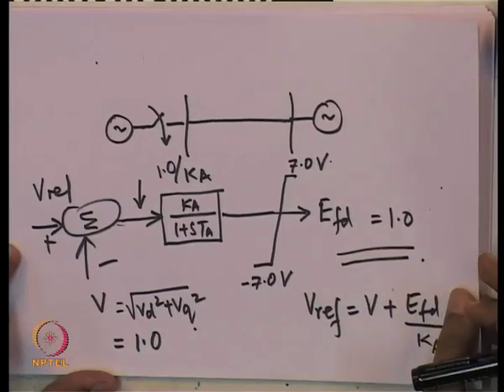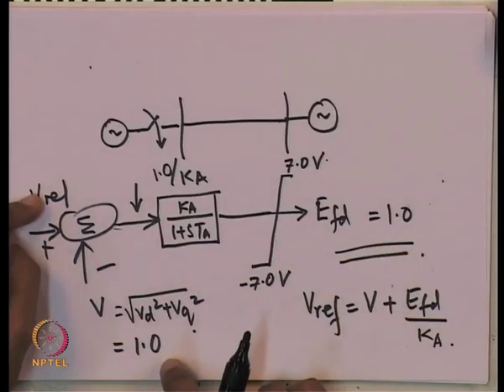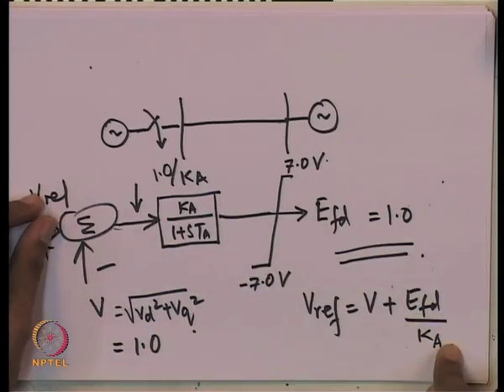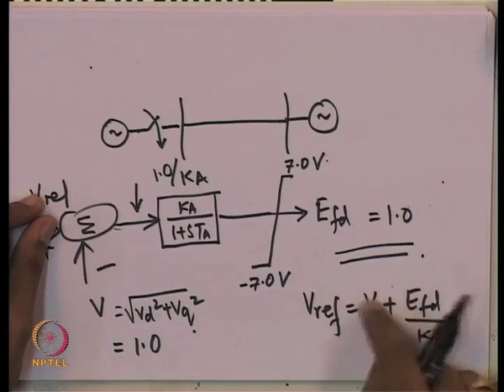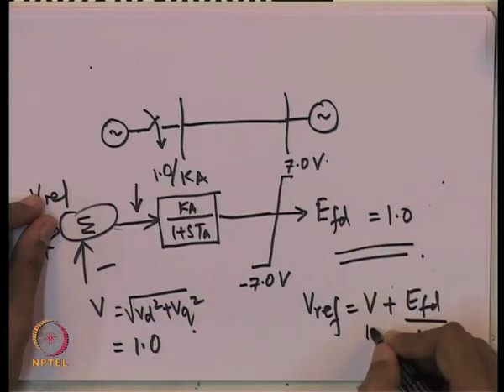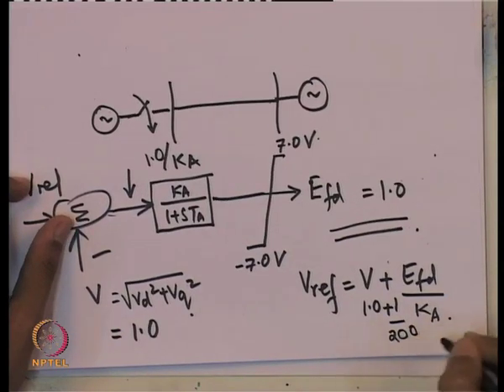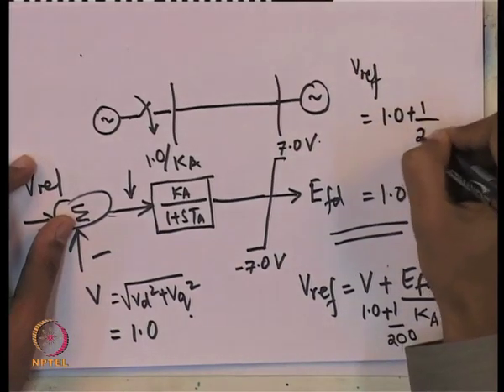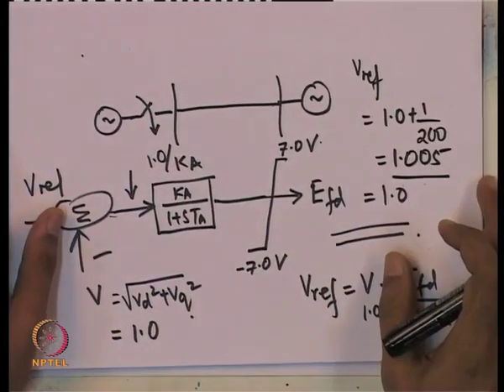Vref can be back-calculated: it is slightly greater than 1. If KA is 200, which is a typical gain in per unit per per unit, then Vref equals 1 plus 1/200, which equals 1.005. So Vref and V are almost the same provided KA is large, which is indeed the case. KA is normally quite large.